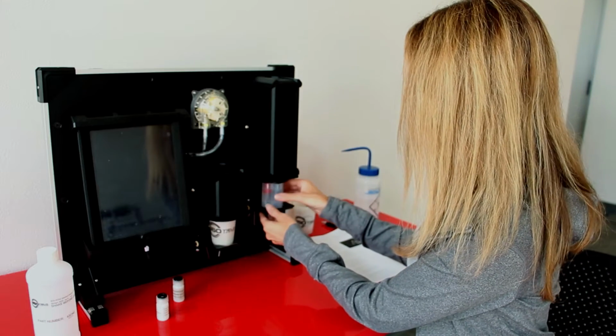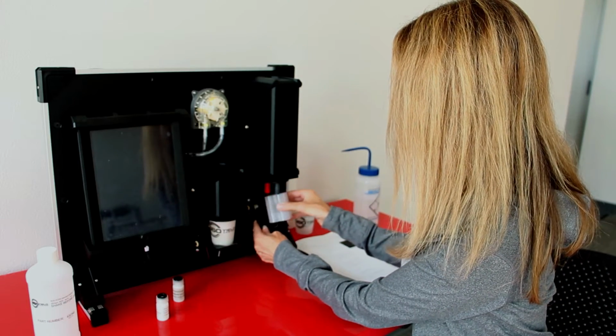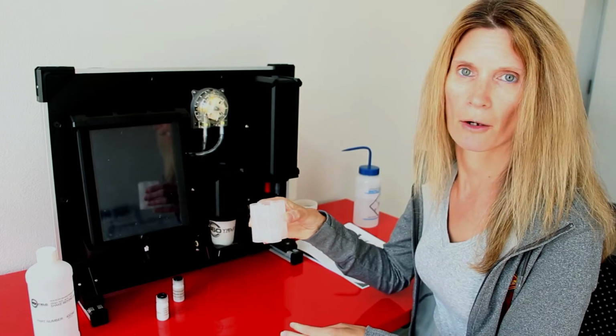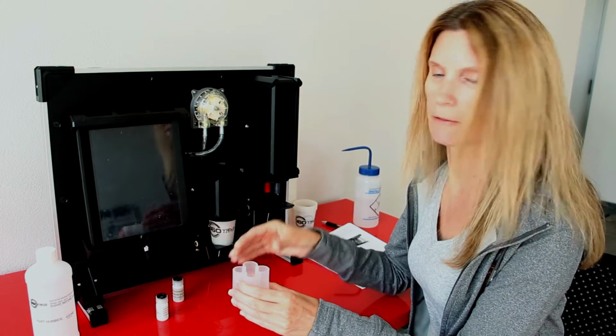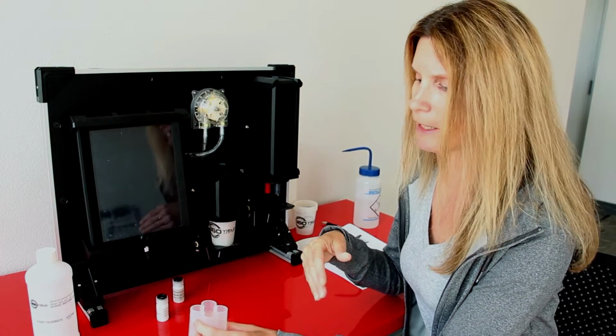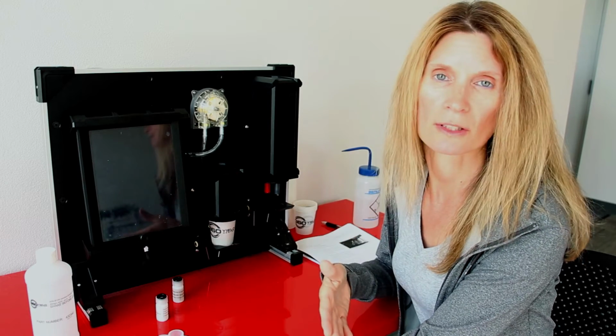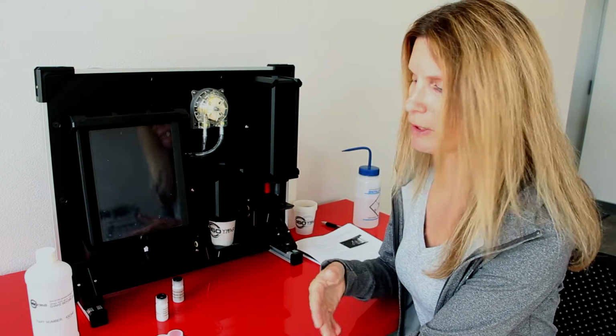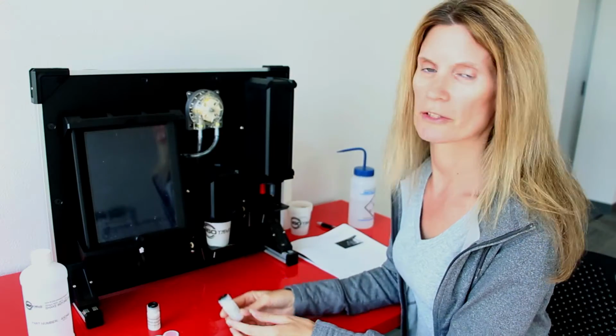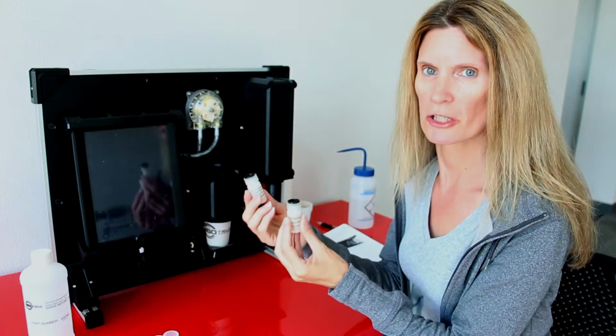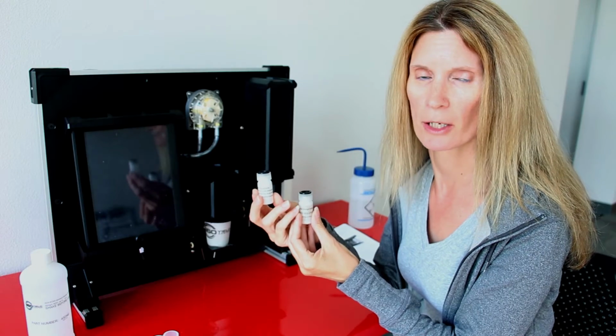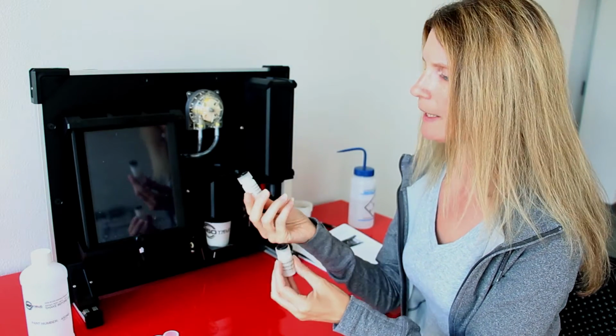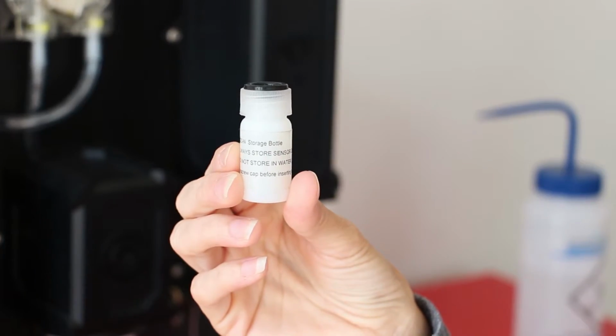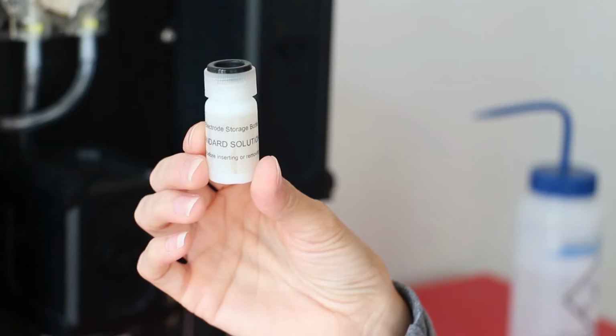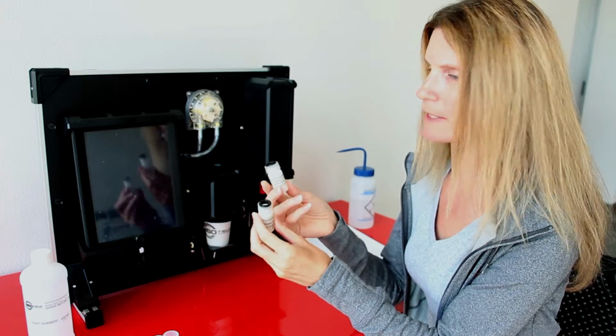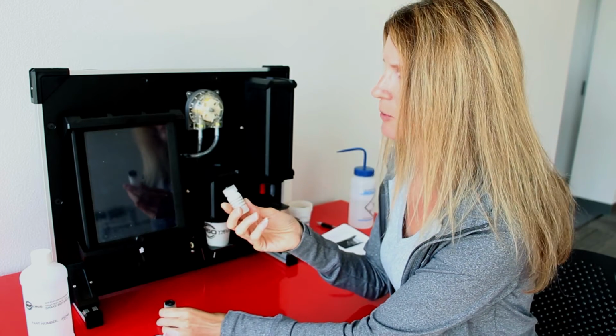So the first thing you'll need to do is just remove the calibration bottle. Go ahead and dump out the standard solution that's in there, and feel free to rinse it out and clean that out so that when you come back to it in the spring next season you'll be ready to go with a clean bottle. And what we're going to do is take our long-term storage bottles. These are the storage bottles that came on the sensors when you received the machine, and we have an NO3 storage bottle here, and we have a storage bottle for the reference electrodes. So we're going to take both of these and just put them back on the machine.